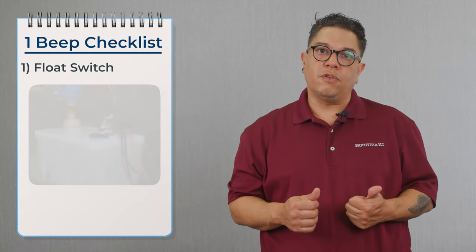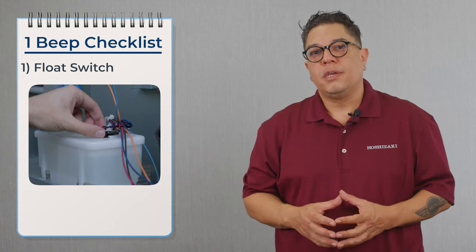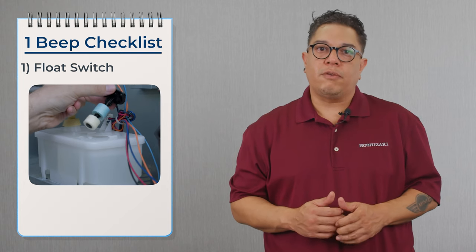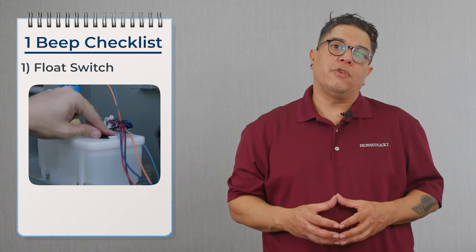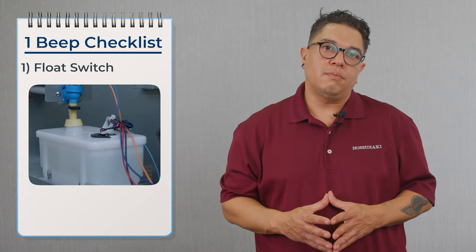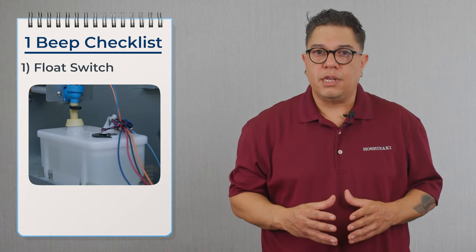The things that we're going to check: we're going to confirm that the float switch is working. The float switch on this machine is a dual float. It has three wires coming off of the top. You have an upper float and a lower float. Your black wire is your common. Your red and blue wires are going to be your upper and lower float. You're going to test each float with continuity 10 times in a row. Up is closed, down is open. If it fails once, it's getting replaced.